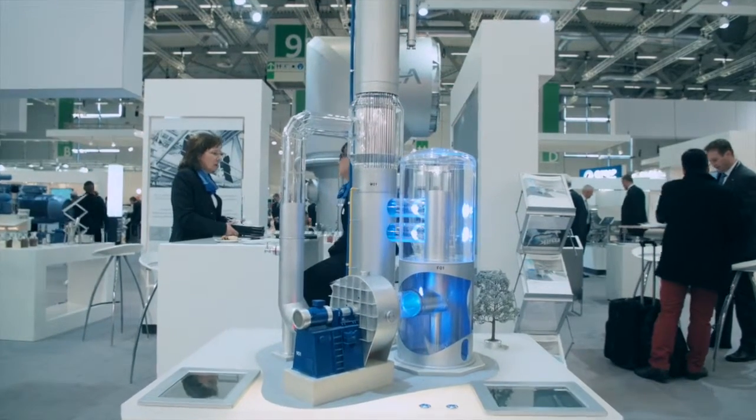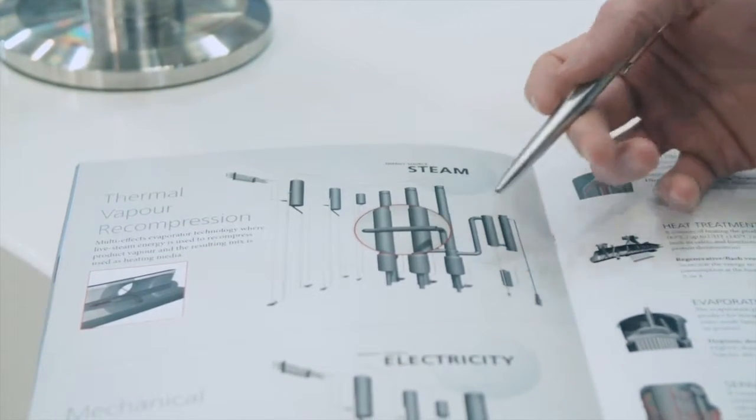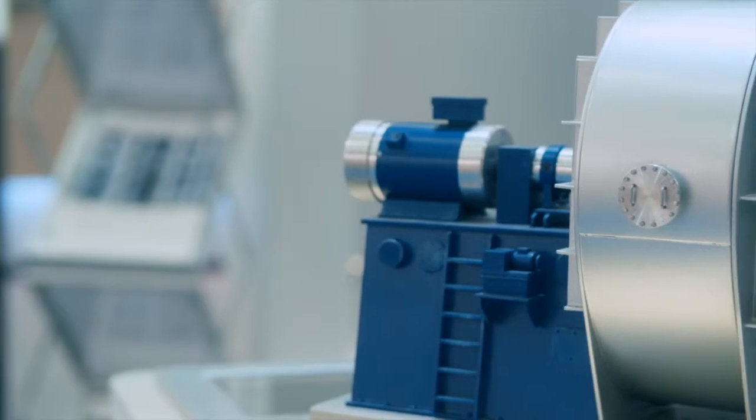The principle behind this technology is that usually in a falling film evaporator you have several calandrias, what we call effects, and a calandria can be a pretty big component — up to three meters in diameter, up to 20 meters high. When you have two or three different calandrias it can take quite a significant place. The principle of the combi-evaporator technology is to combine several effects into one single body, leading to a more compact design.